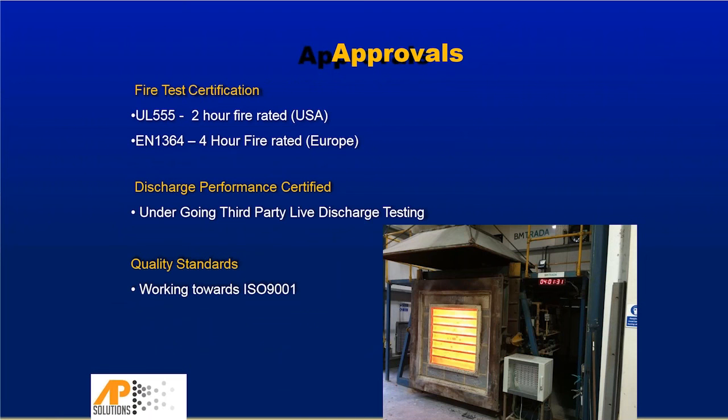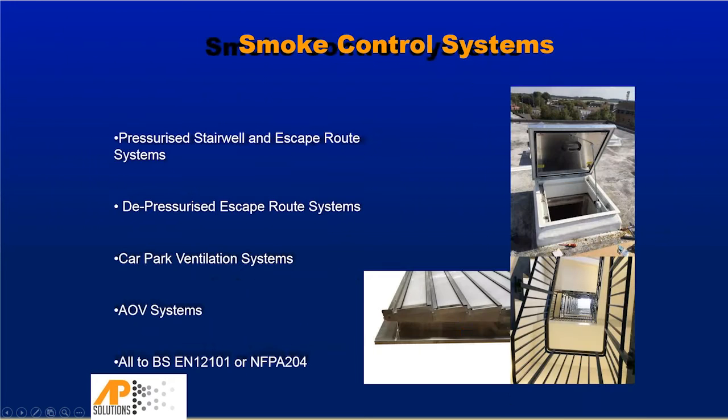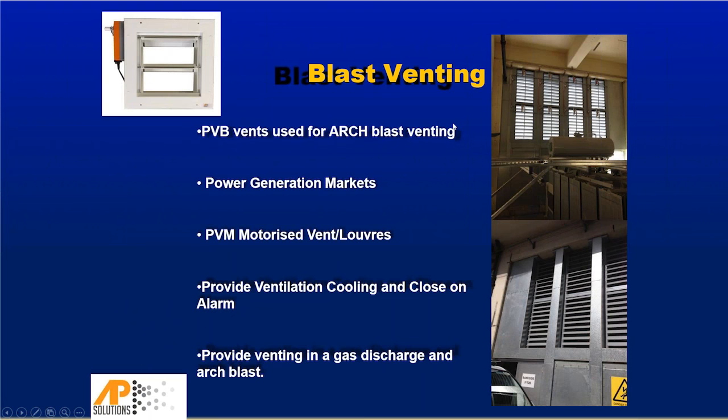Move on quickly to blast venting, knowing that we're running out of time here. We provide, not just for blast venting, but also for pressure venting, motorized pressure vents. For example, if you're pressure venting a room and the customer is trying to keep the number of penetrations in that room to a minimum, we can use the existing air conditioning ductwork as long as it can be shut off and given a path to atmosphere by installing fire-rated motorized pressure vents.